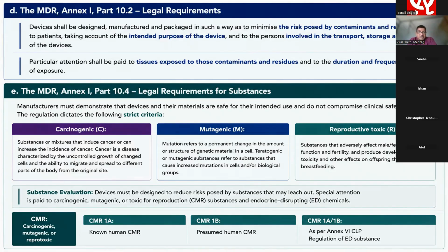Again, Section 10.4 talks about the requirement to identify whether any device or substance, or their materials, or any manufacturing process used along with manufacturing aids or consumables, falls under the carcinogenic, mutagenic, and reproductive toxic categories or not. It is known as the CMR substance, that is carcinogenic, mutagenic, and reproductive toxic substance. So it is required to understand the overall manufacturing process along with the design of your device. So are we following in this category or not? If your device has this type of category, you must involve a toxicologist for the safety evaluation of your device. So the carcinogens are mainly categorized in class 1A, 1B, and 1A and 1B both.